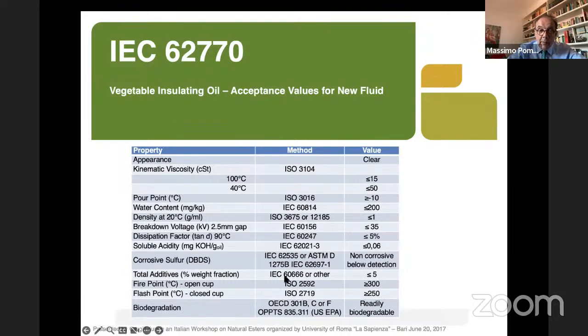Please remember this number: fire point or flash point must be higher than 300 degrees. Is very big number, because remember that in transformer, the risk to have a fire is very important. And if you are using a liquid using a very high flash point, this risk is reduced. Don't forget for a while that we are using a large quantity of insulating liquid.